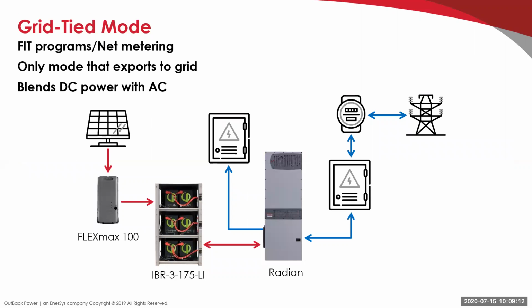The one mode I did want to touch on specifically as to how it works is the grid tied mode. It is the only mode that exports to the grid. Everything else tries to draw primarily, if not only, from the PV and the batteries. In this mode, the Radian will basically act as a grid-tied inverter when the critical load panel is being properly powered and the batteries are fully charged. Excess will sell to the grid.